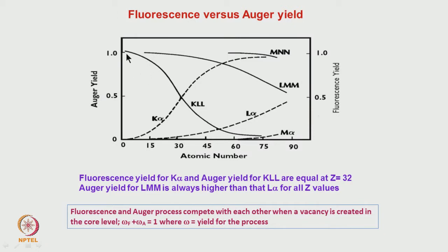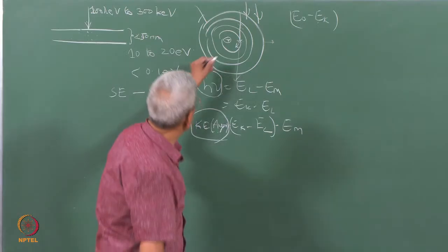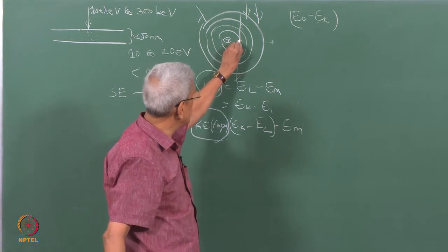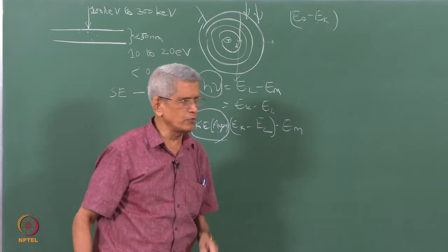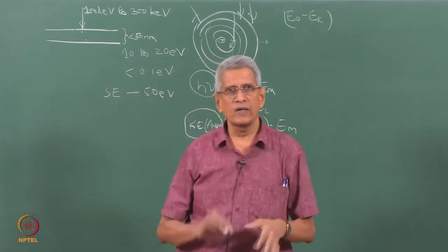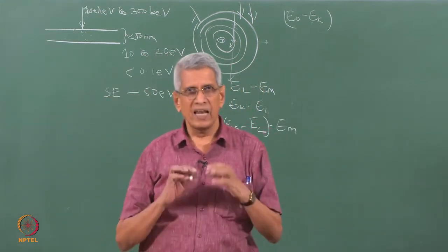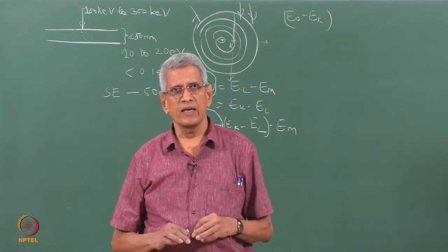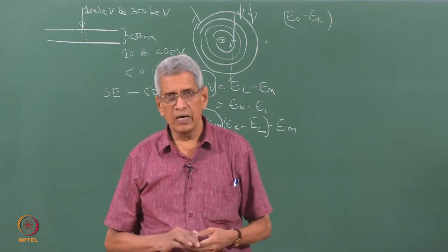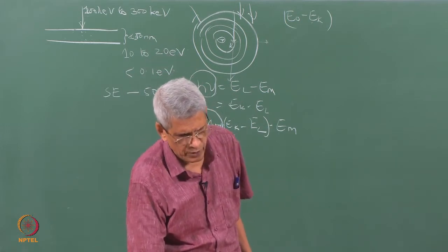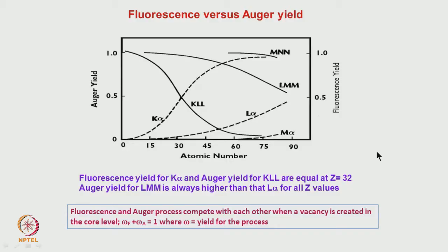That means that when the energy loss of the primary beam is taking place, this is not that sensitive to the atomic number of the elements. Because of that, we can detect light elements as well as the heavy elements with very high sensitivity. Okay. So, this is one of the advantages, that yields could be used to get the concentration of light elements like carbon, nitrogen, oxygen in the sample.